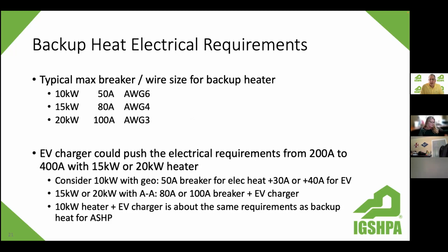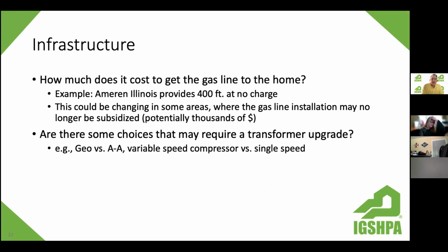So we might be able to get by with 200 amp electrical service and an EV charger if we have the geothermal backup heat. Whereas we could potentially push our customer from a 200 amp service to a 400 amp service if we need that great big electric heat on the air source heat pump and we want an EV charger. So now we've got to consider the heat pump, the electric heat, the EV charger, the range, the dryer, all the electrical loads, plug loads of the house. This is something we really should consider when we're comparing costs. Not only do we know that it's $7,500 cheaper to build the house all electric versus gas, but now when we compare to an air source heat pump, we may have some cost that could involve electrical upgrades, and certainly copper wiring is not getting any cheaper. So just something to keep in mind there.